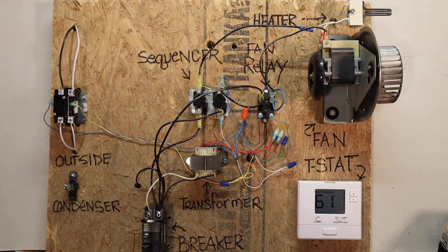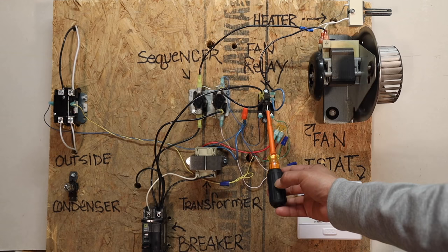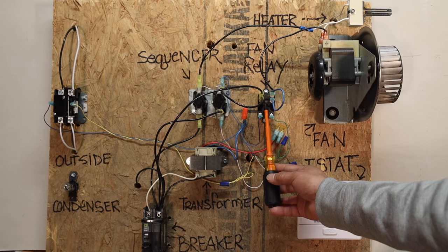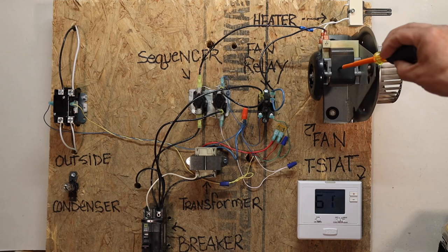So when you turn on the air conditioner, pretty much everything that I just told you still happens. Here you have that 24 volts being applied here, the bimetal goes up and closes this normally open circuit and turns on the blower motor.